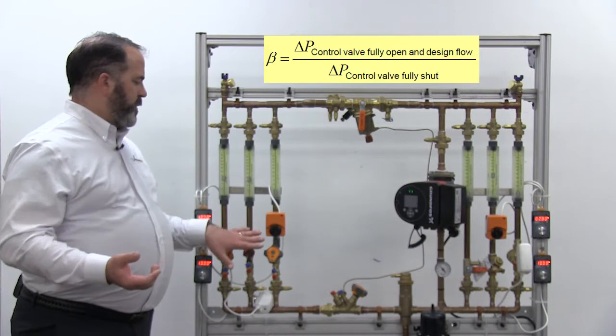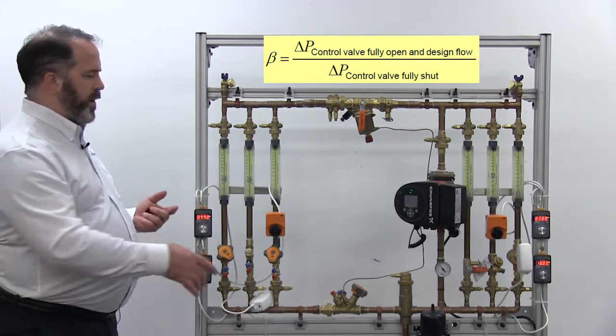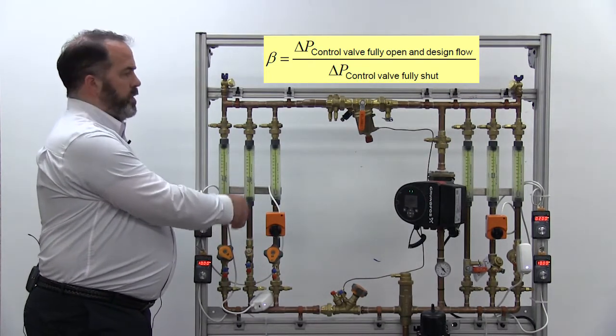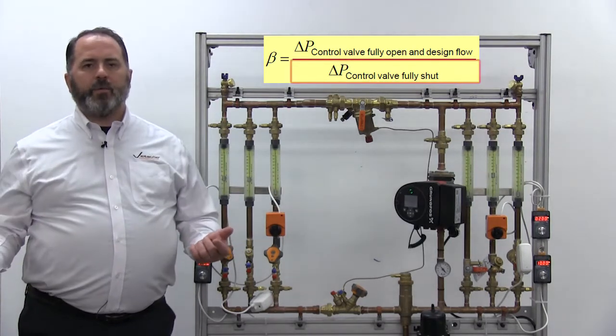Now, if you go to calculate the authority for our TBVCM control valve here, so I'm totaling up all the frictional losses through the pipe, my losses through the coil, all the fittings, everything throughout that system becomes the denominator in that equation.